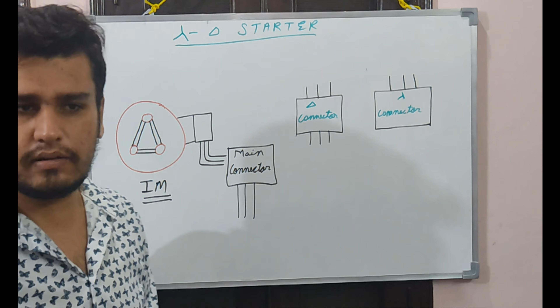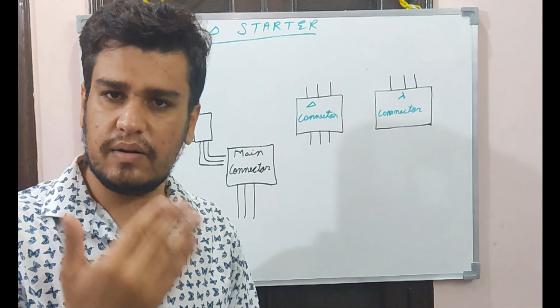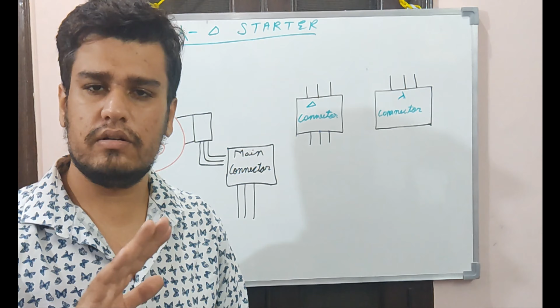The star delta connection is a little bit complex, but the basic idea behind the star delta starter for an induction motor is that in the starting we don't want to give current directly to the delta connection, because it will have inrush current nearly 5 times more than the rated current of the induction motor. So first we give supply to the star connection, and when the induction motor achieves 80% of its rated speed, we turn the supply to the delta connector and let the motor run at rated speed.